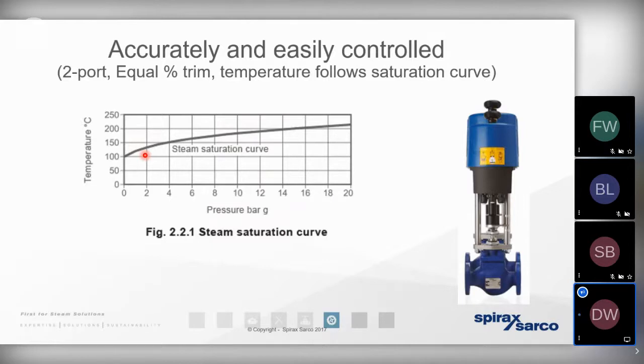Now, one way that we can utilize that pressure temperature relationship at the process, at the heat exchanger, is that we can control the release of heat energy very, very easily by simply using a 2-port valve. It can be a self-acting valve, or it can be a control valve, as we can see in the little image on the screen. Because we need to understand that if we've got a certain temperature requirement in the steam, we can achieve that by nothing more than reducing the pressure.